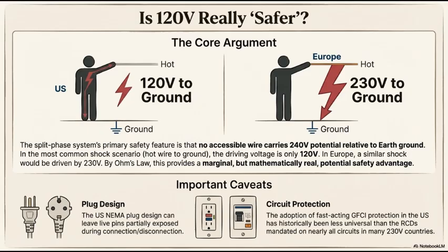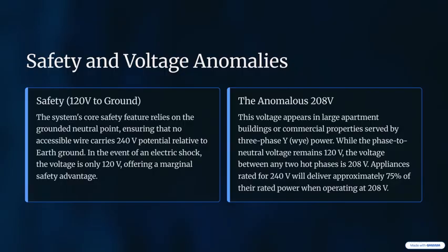Now, why would a 240-volt country intentionally introduce this low-voltage setup for its highest-risk environments? If the efficiency argument were truly paramount, they'd just run 240 everywhere, but they don't. And this validates the core principle. Lower voltage to ground, adhering to Ohm's law, mathematically reduces the potential current during a shock. It maximizes safety where human contact is most likely.